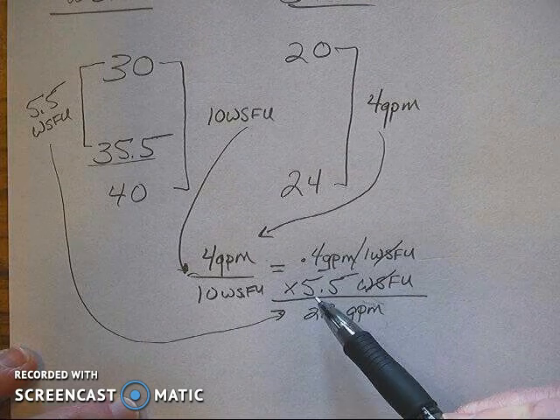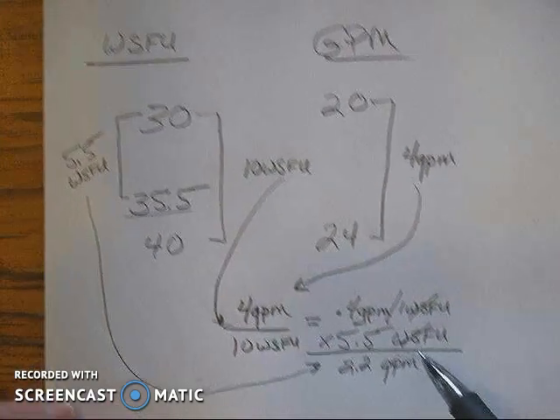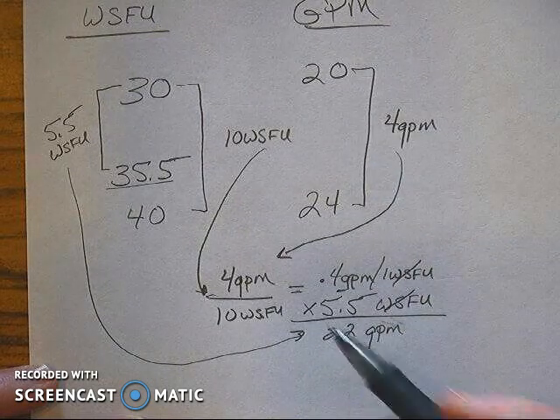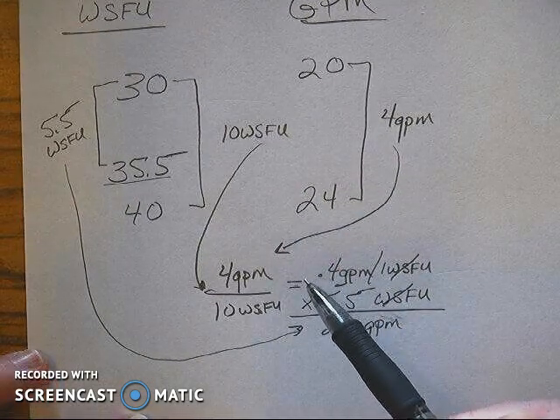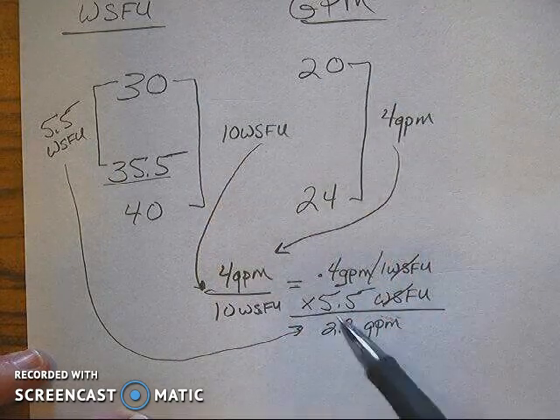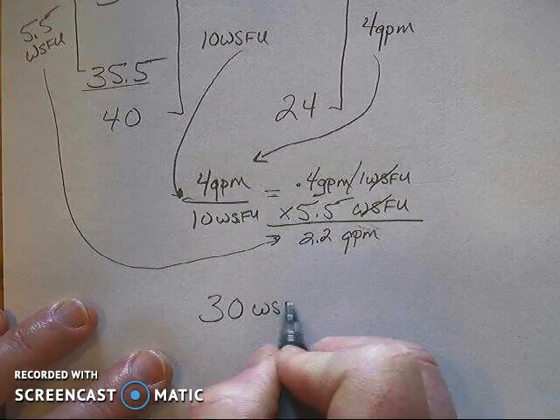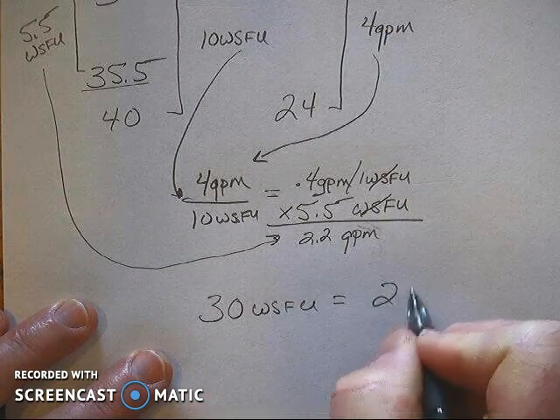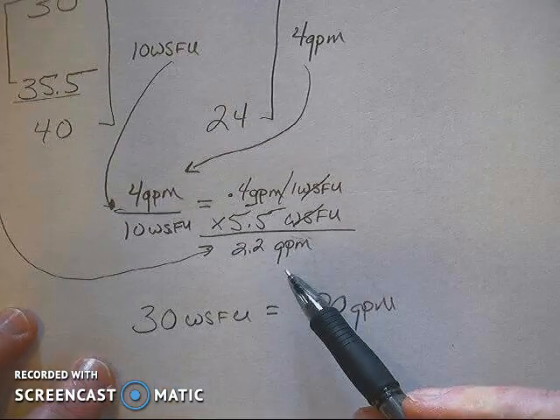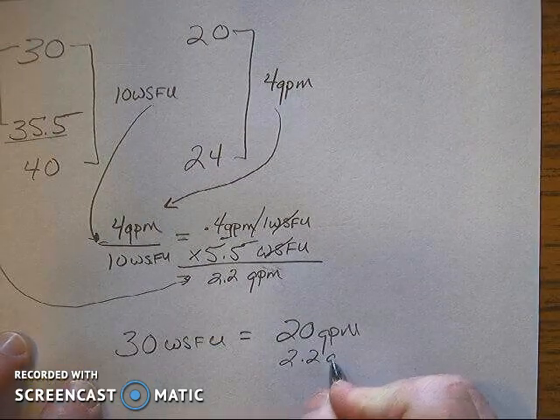In other words if I go up 5.5 WSFU on the left hand side I will go up 2.2 GPM on the right hand side. 30 WSFU equaled 20 GPM. So 30 WSFU equals 20 GPM and we are going to go up 2.2 GPM.